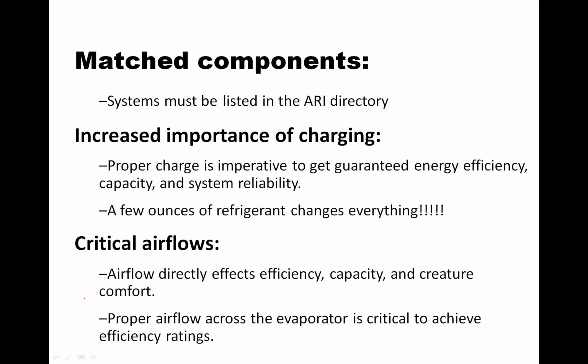Airflows are critical to proper operation of a system because airflow directly affects the efficiency, capacity, and creature comfort. Airflow impacts humidity removal, and if we don't get the proper humidity removal, we get a home that's cold and clammy. Proper airflow across the evaporator is also critical to achieve the efficiency ratings. If we don't have enough airflow across the evaporator, we're going to have low output of the equipment. So we want to make sure that we do that.